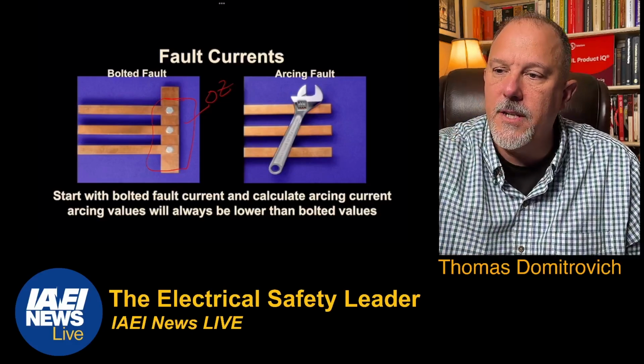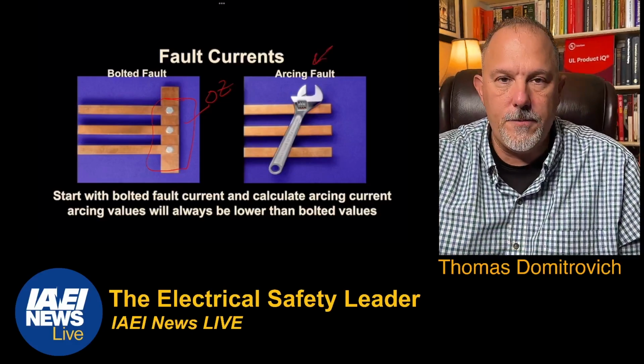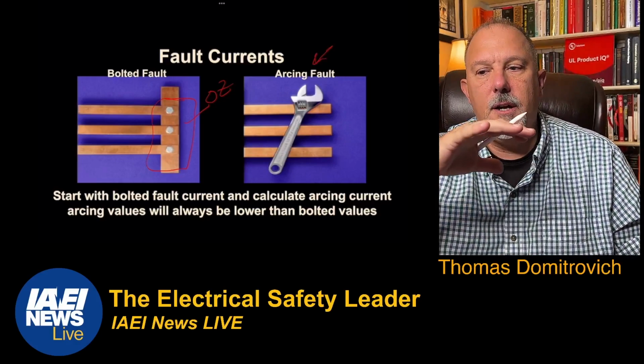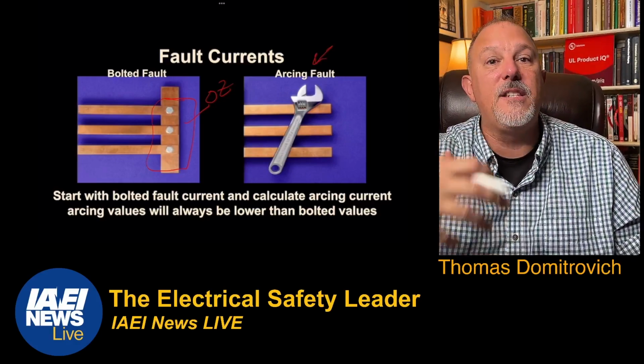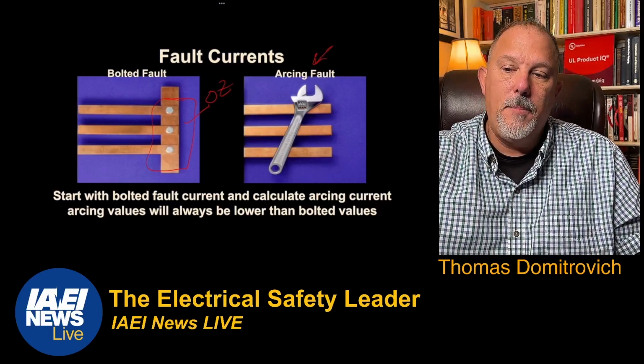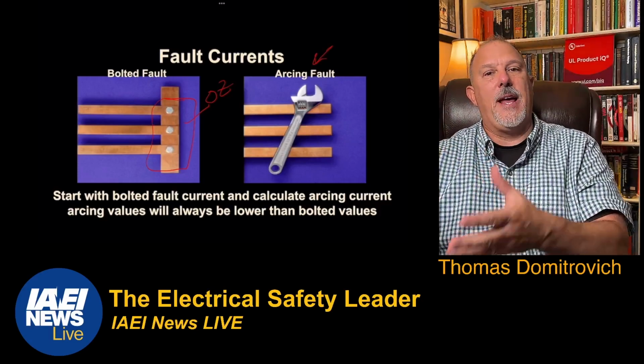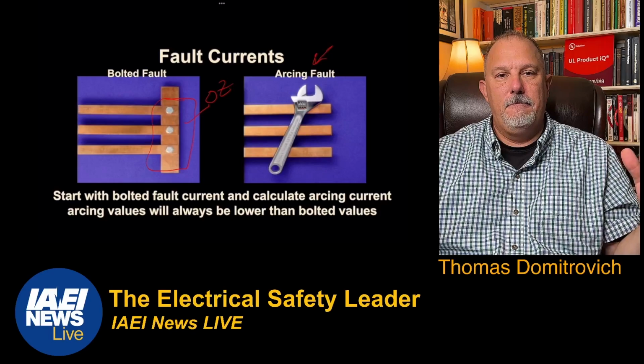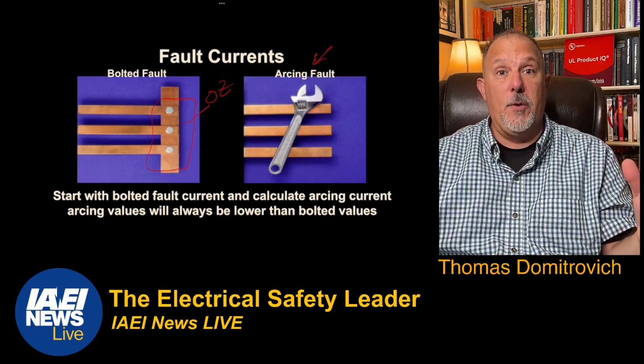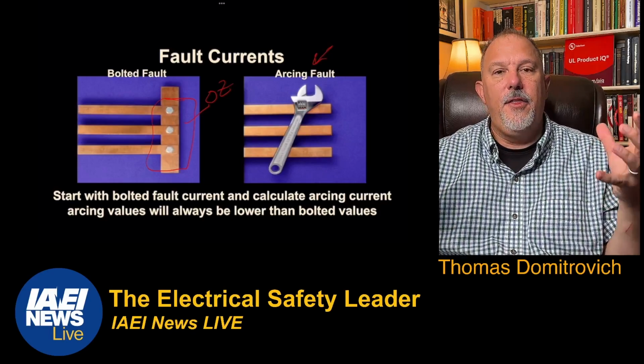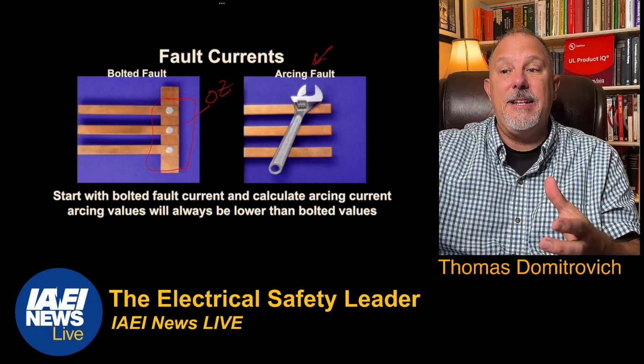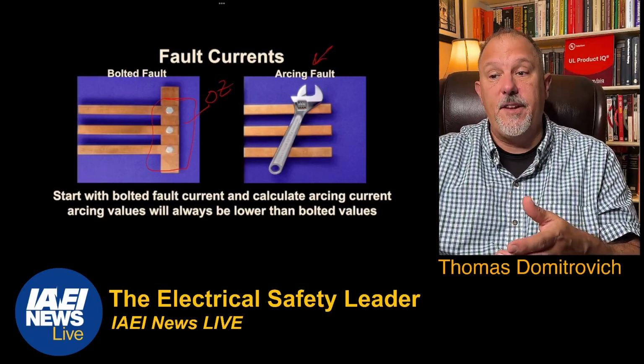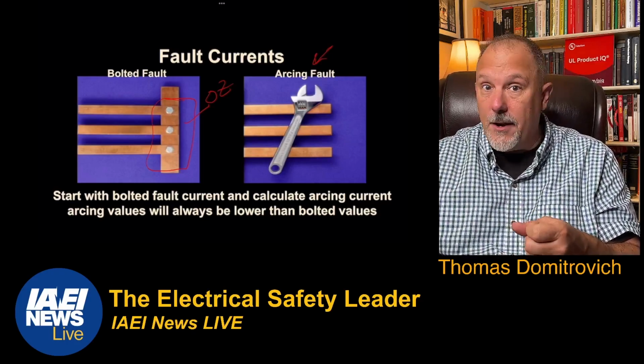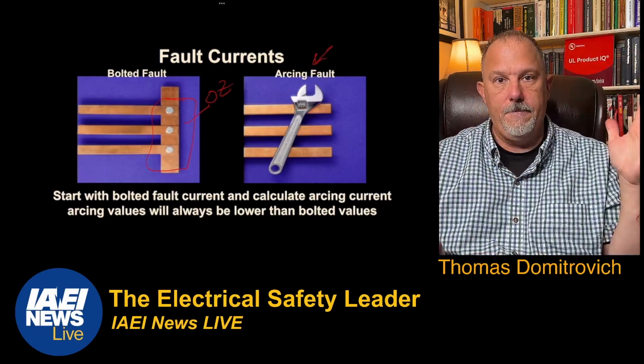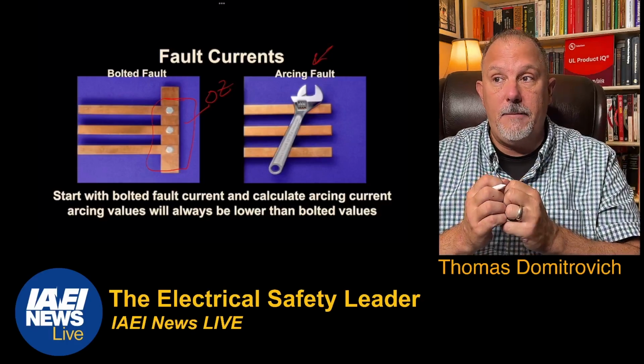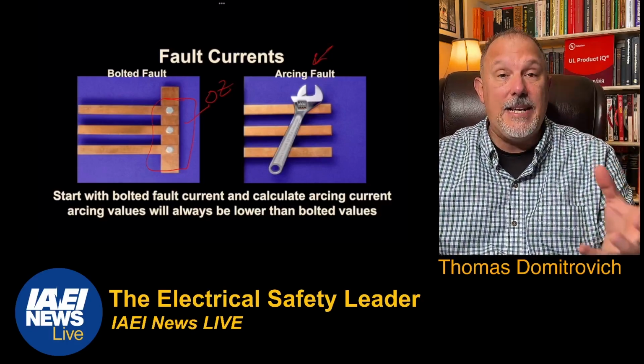This type of fault, an arcing fault, is one that has an impedance value. And we show a wrench. But remember in the beginning when we talked about that plasma cloud, the current flowing through air, that has an impedance as well. If I drop a wrench on 3 phases, do you think that wrench is going to stay there? It's probably going to get blown away. Or it's going to be evaporated because of the heat.